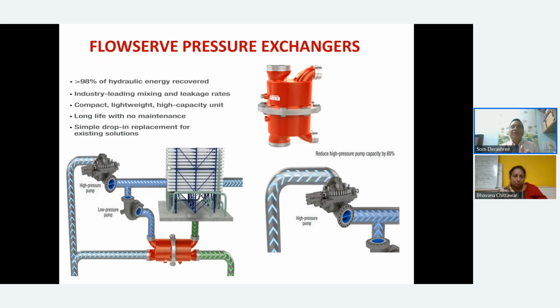And these people have developed this for desalination plants, especially for the Gulf, etc., when you have huge desalination plants. What happens is, this is a pressure exchanger. So the incoming stream exchanges pressure with the outgoing reject. The reject, actually, doesn't need pressure. It has to just go to the ETP, or it has to go back to the sea. And whatever was the pressure is taken up by the booster pump. So almost 98% of the hydraulic power is recovered.